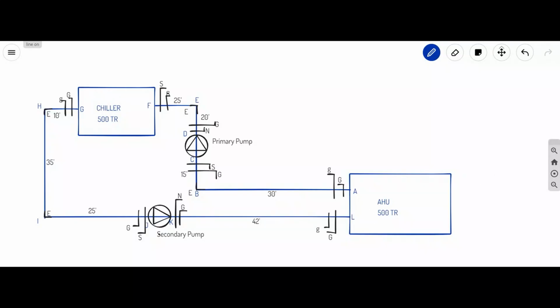Now we need to find out the pipe size for the primary pump and secondary pump. The primary pump supplies chilled water return to the chiller, and the secondary pump supplies chilled water to the AHU. Now E indicates elbow, 90 degrees, long radius. Capital G indicates gate valve. Gate valve is like an isolating valve, so it will start the flow or stop the flow. Globe valve is for controlling the flow.